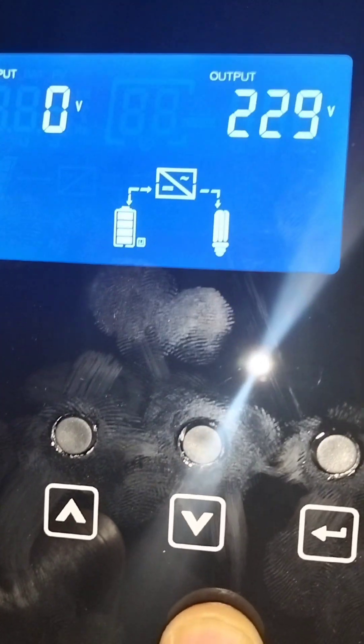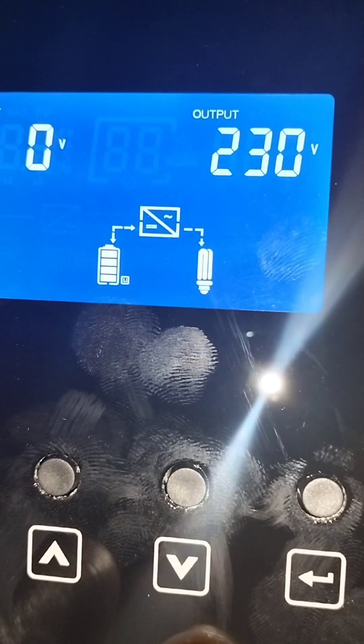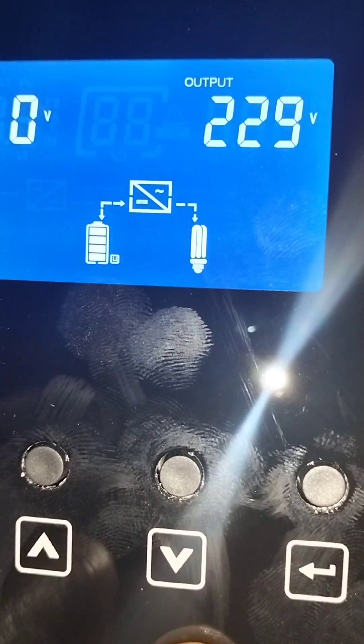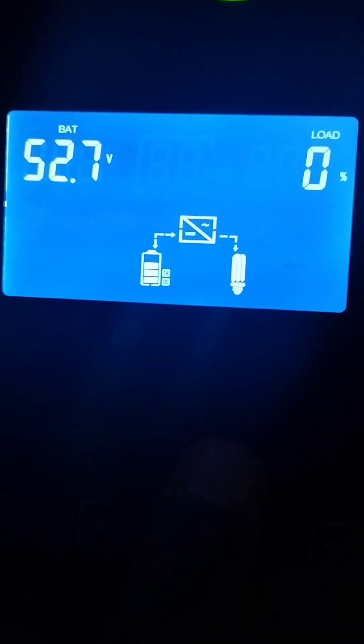Lack of communication is what always causes your inverter to report the battery as full while the batteries are not full. Whenever you are using lithium batteries that can communicate with the inverter, make sure the communication is well connected. The communication has come back now — you can scroll and check. You see it has shown the percentage.